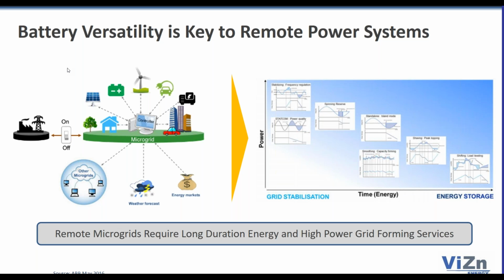You've got various point sources of load—man camps, HVAC, kitchens, a bunch of different things driving your demand. But the generator wants to run at a constant RPM. If there's no storage in a microgrid, the generator has to cycle and match the overall power demand.